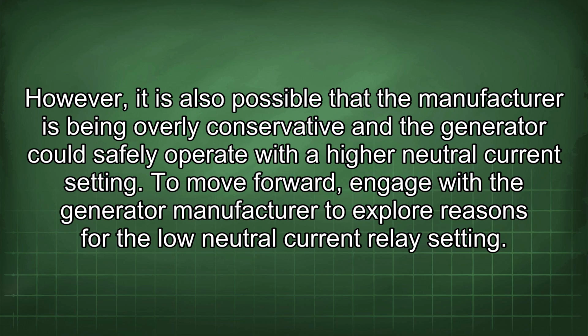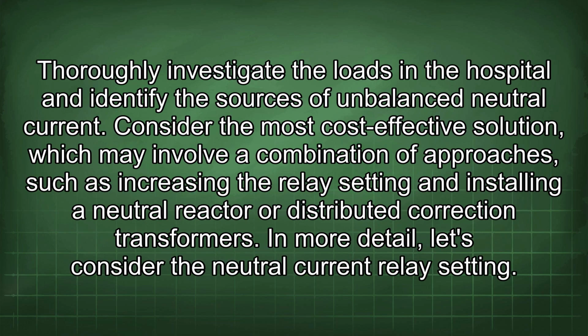To move forward, engage with the generator manufacturer to explore reasons for the low neutral current relay setting. Thoroughly investigate the loads in the hospital and identify the sources of unbalanced neutral current. Consider the most cost-effective solution, which may involve a combination of approaches, such as increasing the relay setting and installing a neutral reactor or distributed correction transformers.